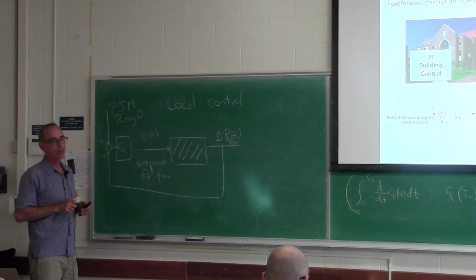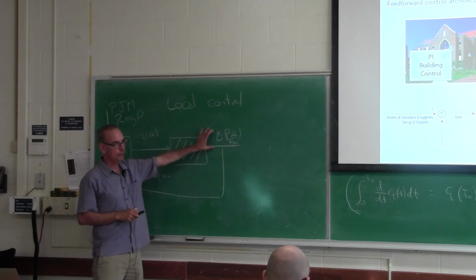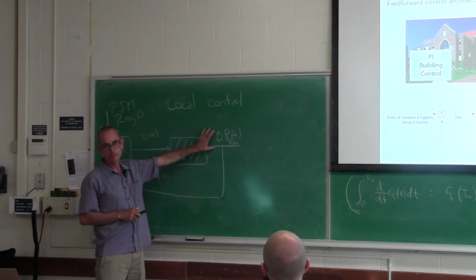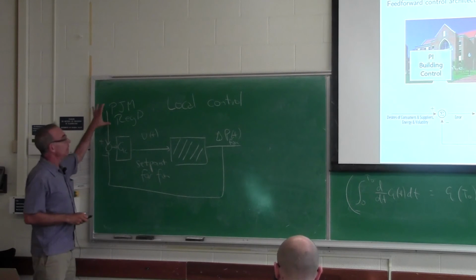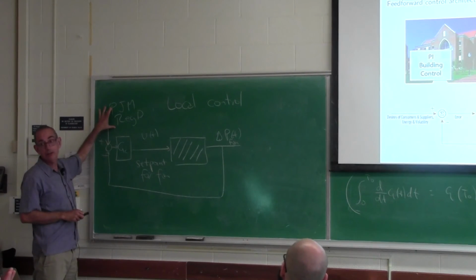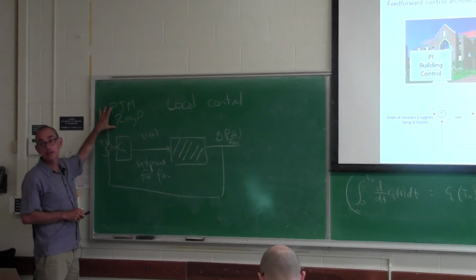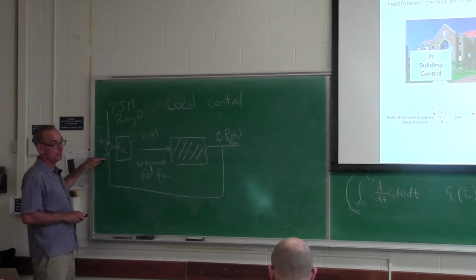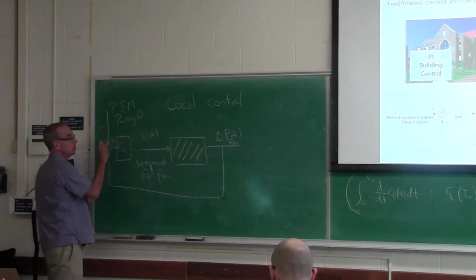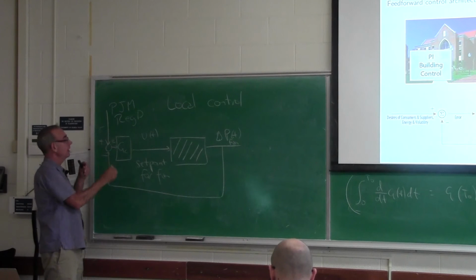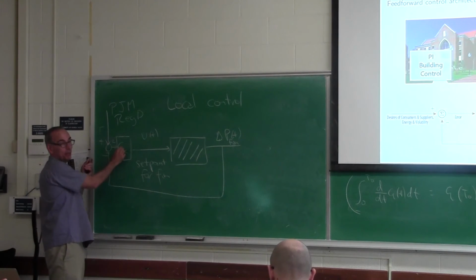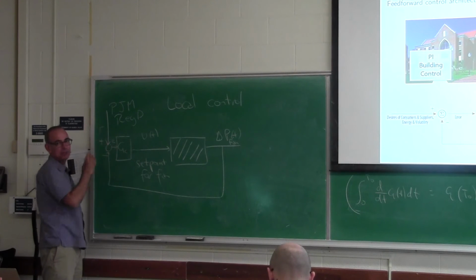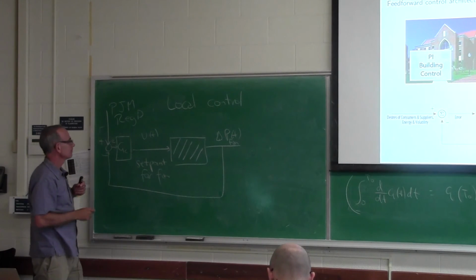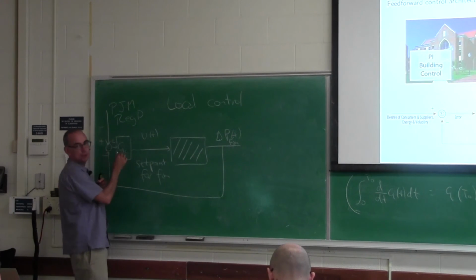So we were able to measure the power deviation from the fan, and we were able to then measure the PJM reg D signal appropriately scaled, and take the difference - which is what we called E before, but this is local, just in one building - and pass it to our compensator. And guess what? PI, just some simple control. I'm sure proportional probably would work as well. And until we could close this loop, it didn't work.